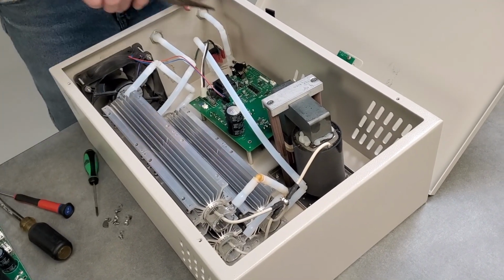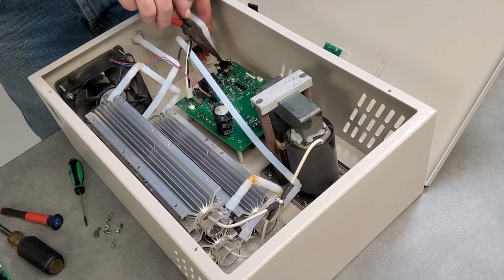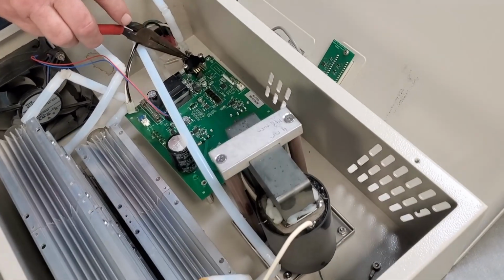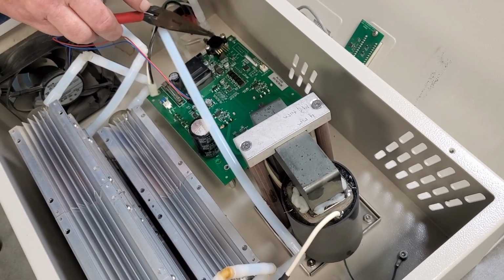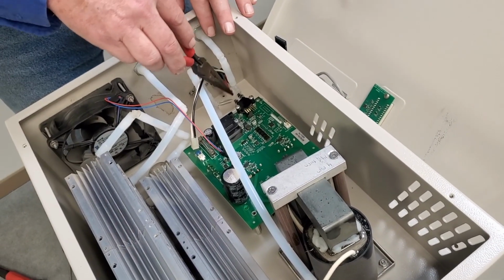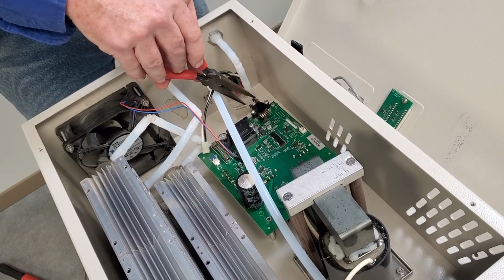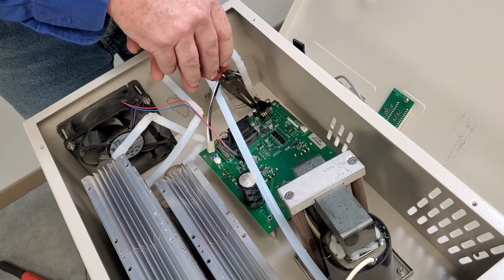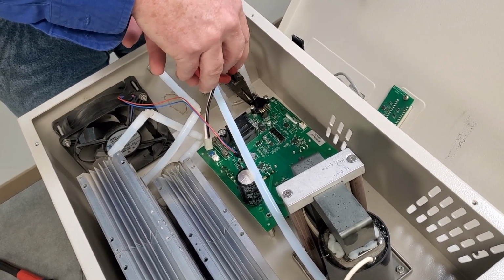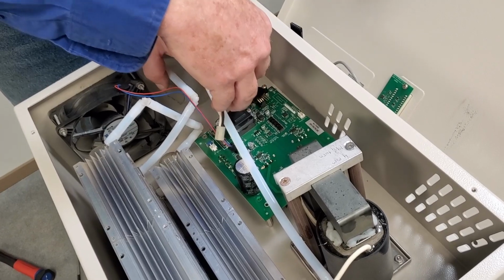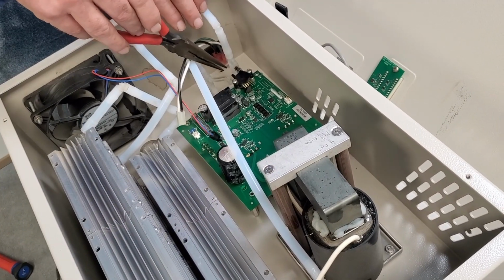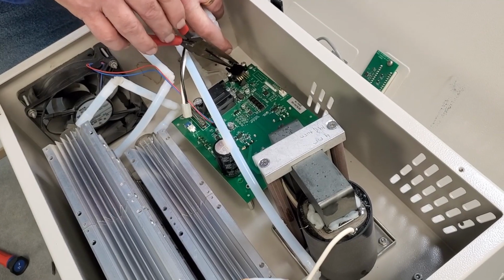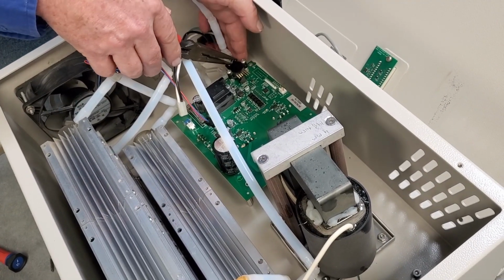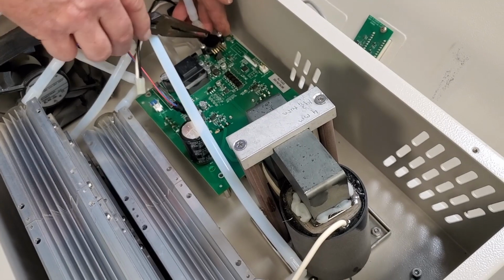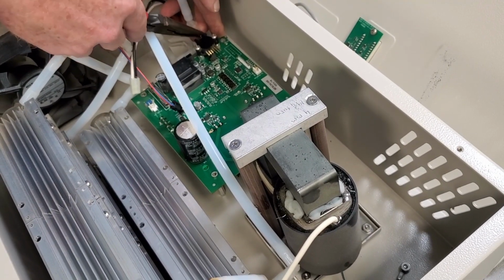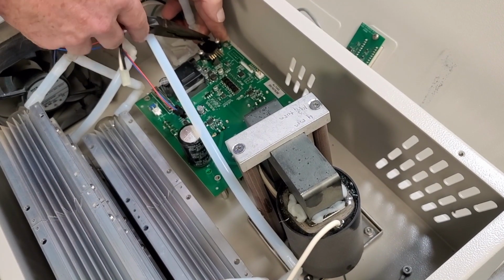A couple of other things I want to show you in here. This is a flow sensor. The oxygen is coming in this tube here, and it detects a differential of pressure. It works best if you can get a little needle-nose pliers between that rubber and gently pry these off. If you try to just pull them straight off, you risk damaging the board. I probably should have done that before I took these screws out, but just wiggle it back and forth a little bit, get it over the edge, and that'll pop off.